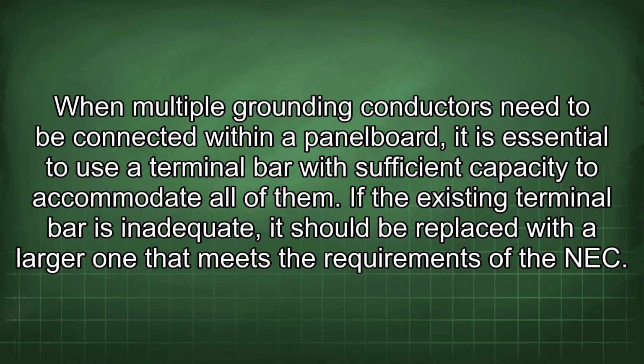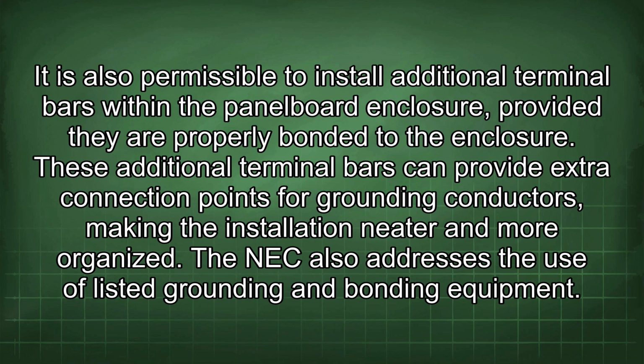When multiple grounding conductors need to be connected within a panel board, it is essential to use a terminal bar with sufficient capacity to accommodate all of them. If the existing terminal bar is inadequate, it should be replaced with a larger one that meets the requirements of the NEC. It is also permissible to install additional terminal bars within the panel board enclosure, provided they are properly bonded to the enclosure. These additional terminal bars can provide extra connection points for grounding conductors, making the installation neater and more organized.